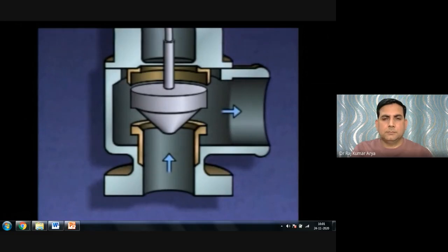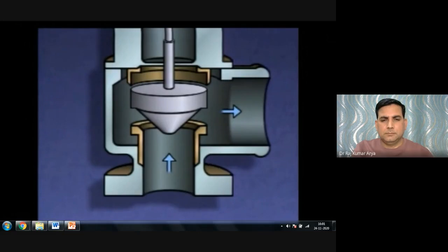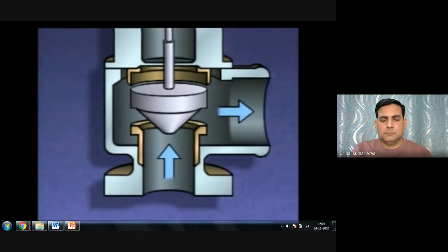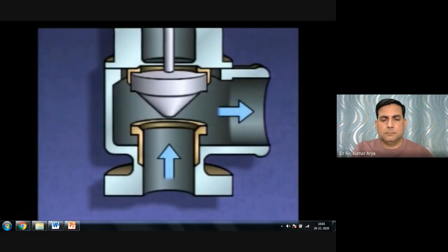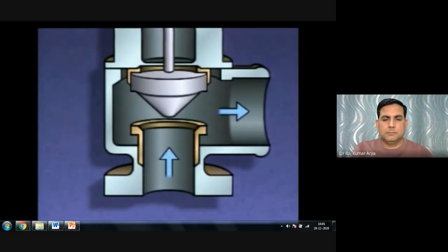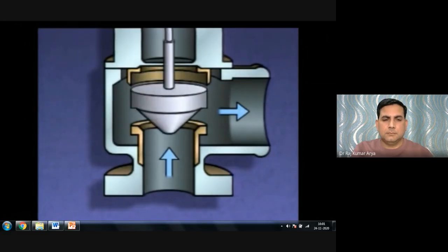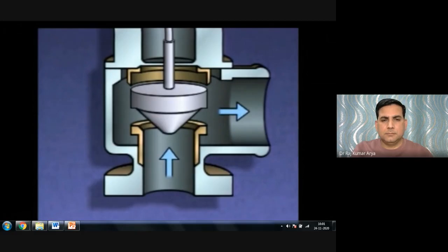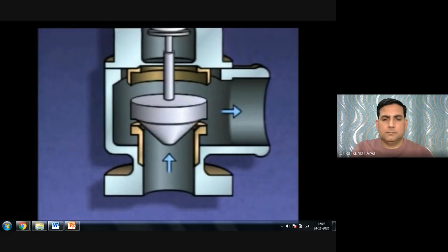As system pressure continues to rise, the pressure acting on the bottom of the disc increases further, causing it to lift even higher. Once the excess pressure has been relieved, system pressure begins to drop, and the force on the disc decreases. However, when system pressure drops back to the pop-open pressure of 200 psi, the valve still doesn't close because the lip of the disc remains exposed to the pressure of the escaping liquid or gas. The valve won't close until system pressure drops below the pressure needed to pop it open.